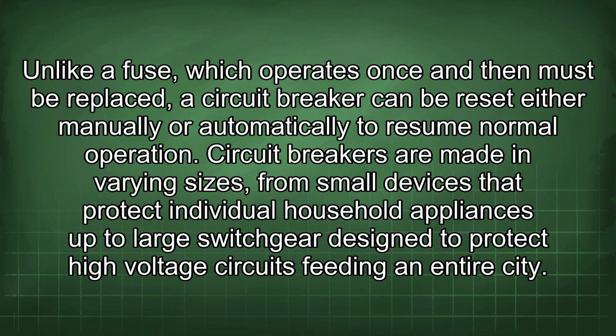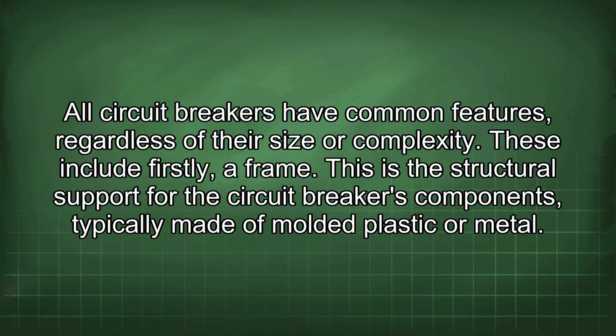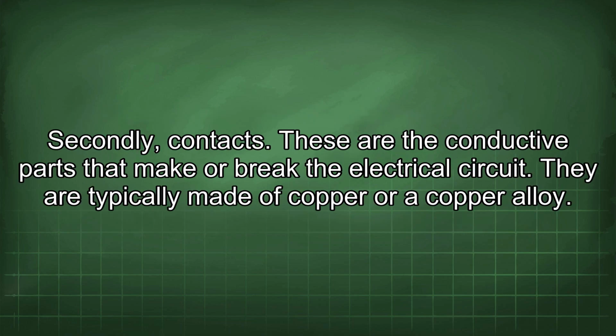Circuit breakers are made in varying sizes, from small devices that protect individual household appliances up to large switchgear designed to protect high-voltage circuits feeding an entire city. All circuit breakers have common features, regardless of their size or complexity. These include, firstly, a frame. This is the structural support for the circuit breaker's components, typically made of molded plastic or metal. Secondly, contacts. These are the conductive parts that make or break the electrical circuit. They are typically made of copper or a copper alloy.